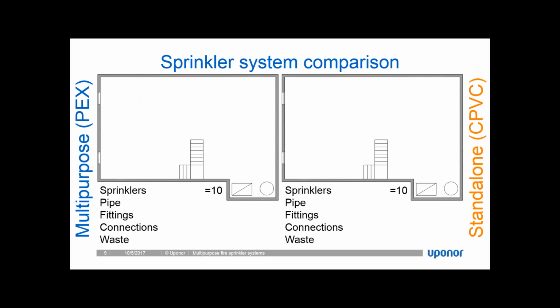So when we pop down to the basement, things are going to change a little bit, and this is the first time where we start to split paths from a sustainability standpoint, because we're going to start using more material on the standalone side. Down below, I've added another 7 sprinklers on the multi-purpose side and an additional 9 sprinklers on the standalone side.